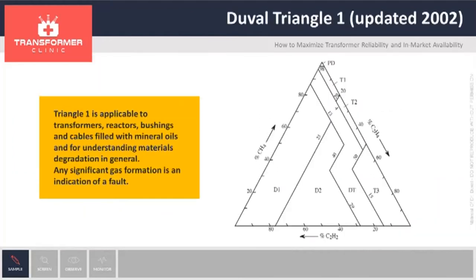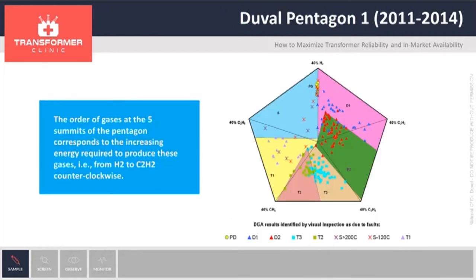Triangle 1 uses methane CH4, ethylene C2H4, and acetylene C2H2. Triangle 1 is useful to distinguish between the six basic types of electrical and thermal faults. Pentagon 1 is also able to identify the six basic types of faults, plus stray gassing of oil S.